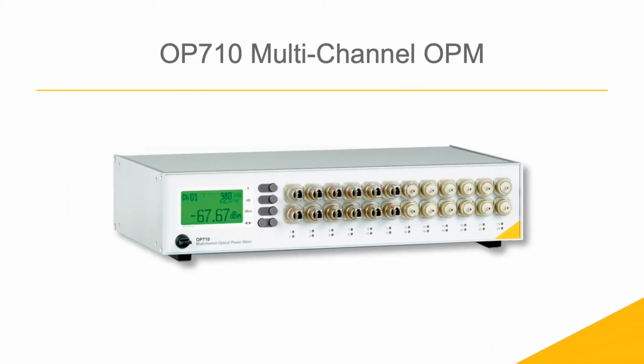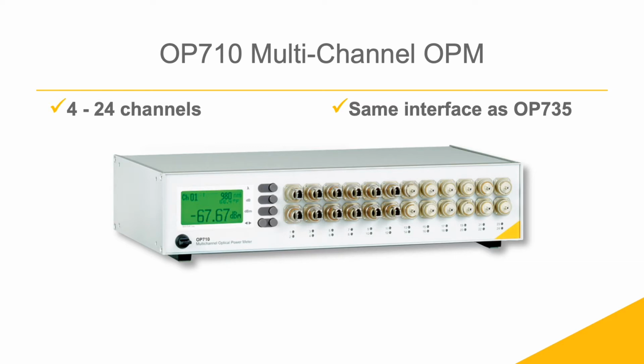The OP710 is a rack-mountable version of the OP735 that supports up to 24 channels of simultaneous testing. The internal display shows results for a single channel at a time, but the software allows viewing of all channels simultaneously. Its utilitarian design and high channel count make it OptoTest's most popular model.